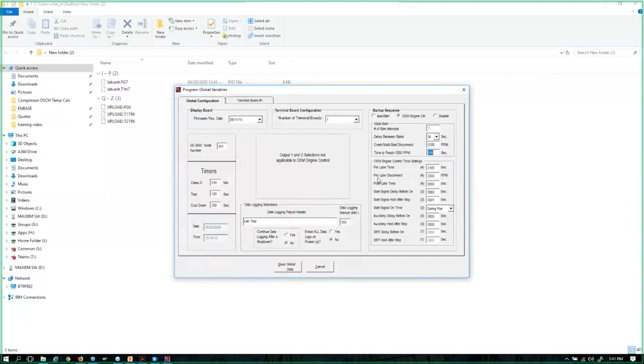Again, just like the auto start attempt, I have a pre-lube disconnect RPM that I can enter in. And a lot of times I'll use this number as a low value, because I know I'm usually cranking faster than 150, and maybe I want to drop out the pre-lube pump while I'm cranking to free up extra volume for the starter on an air system.